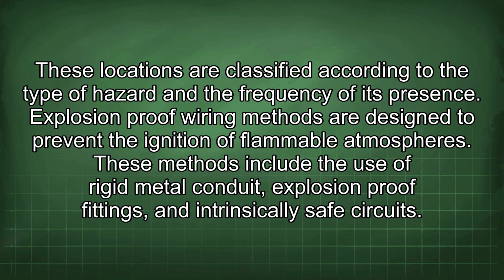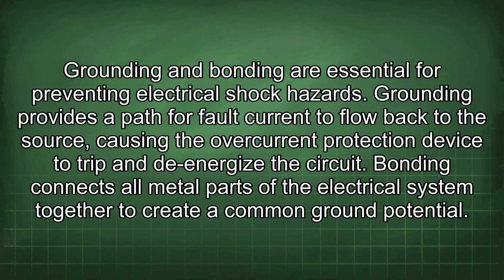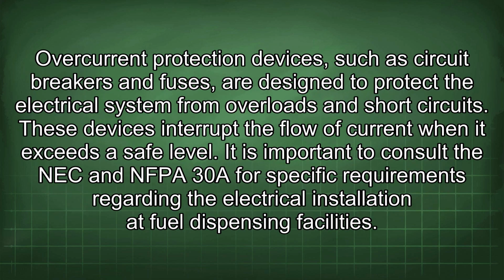Explosion-proof wiring methods are designed to prevent the ignition of flammable atmospheres. These methods include the use of rigid metal conduit, explosion-proof fittings, and intrinsically safe circuits. Grounding and bonding are essential for preventing electrical shock hazards. Grounding provides a path for fault current to flow back to the source, causing the overcurrent protection device to trip and de-energize the circuit. Bonding connects all metal parts of the electrical system together to create a common ground potential. Overcurrent protection devices, such as circuit breakers and fuses, are designed to protect the electrical system from overloads and short circuits. These devices interrupt the flow of current when it exceeds a safe level.